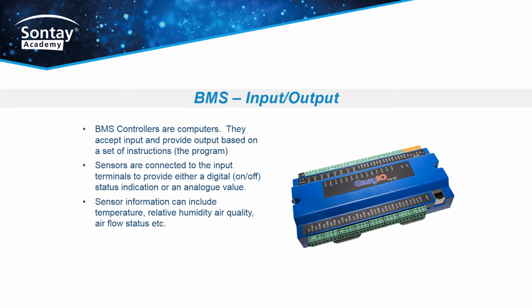BMS inputs and outputs. BMS controllers are computers. They accept inputs and provide outputs based on a set of instructions, which we refer to as the program. Sensors are connected to the input terminals to provide either a digital, on and off status indication, or an analog value. Sensor information can include temperature, relative humidity, air quality, and airflow status, but there are many others.